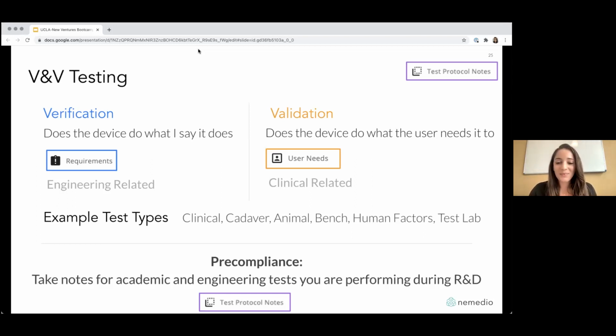So this is a tricky topic. How can I best explain this? The idea is that you're basically taking a shortcut by using a standard. So you're saying my device is compliant to electrical safety standard IEC 60601-1. The United States doesn't specifically say you need to test to this standard. The United States says your device must be electrically safe. And the industry agrees that in order to demonstrate electrical safety, you comply with this international standard.